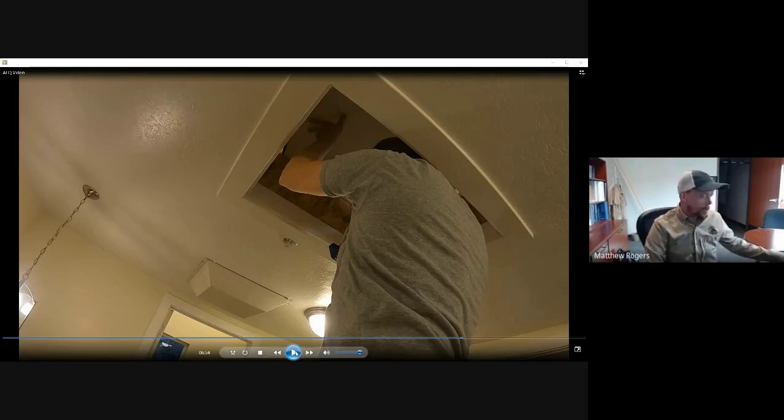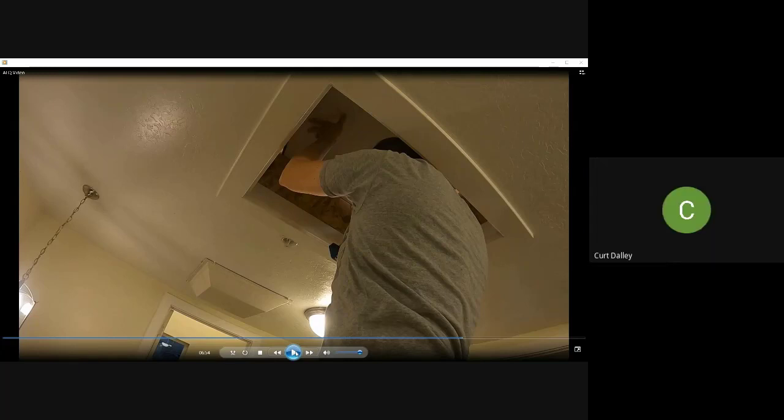If you're going to use the chart in the Home Performance Diagnostics book, the RedCalc will still work. I just found it works a little better, it's less touchy, if you get a pressure difference of at least 10 pascals. So if you're not getting enough pressure difference, you can open your door between your zone and your house a little more. Did that answer your question? Yeah. Okay.